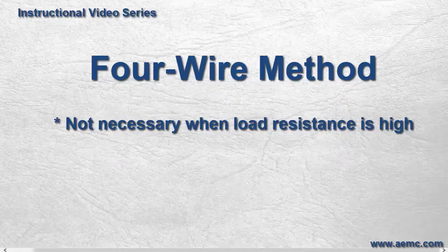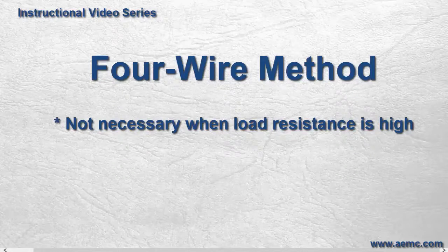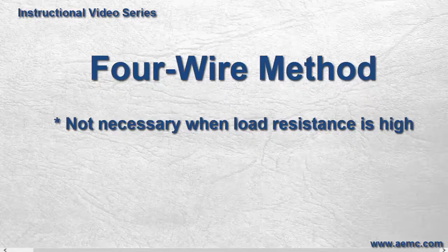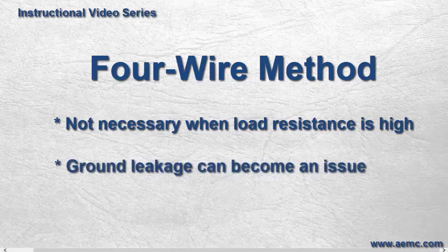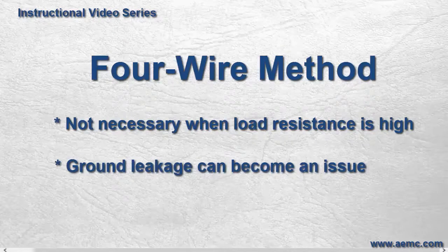Further, measuring high resistance loads requires that the constant current be kept at very low levels. As a result, ground leakage resistance can become a significant contributor to the overall resistance measurement, rendering the measurement inaccurate.